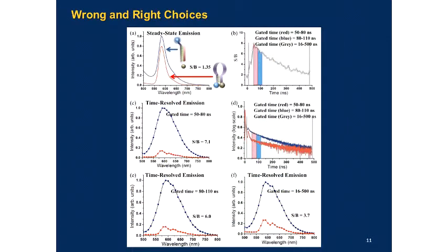But this is in the theoretical case. In the actual case, when you do this experiment in the spectrometer, you have to add a new constant, which we call y. And you might ask why, and I will tell you that it is because you always have a non-specific background due to dark noise, dark counts, light percolating into the system, many things.